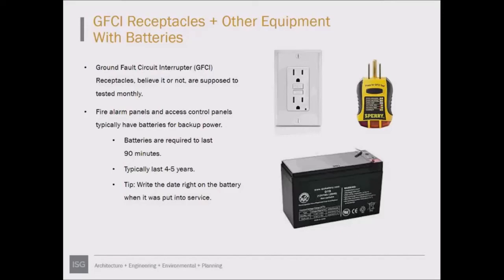Ground fault receptacles are also supposed to be tested monthly—it says so right on the device. There are inexpensive testers, like the one pictured in the top right corner, that you can purchase, or you can just push the button right on the receptacle. If the trip does not reset, the device needs to be replaced.